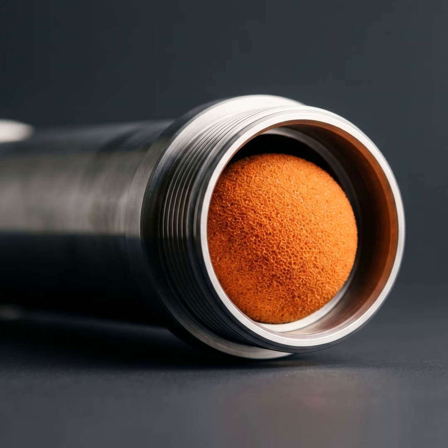It is the ultimate marriage of the digital and the physical realms. It really is. You have the software logic telling the system exactly when to release the balls, meticulously managing the 30-minute intervals, monitoring the flow rates. Right. And then you have the physical friction of the neoprene actually doing the dirty work that a human used to have to do with acid. And the net result is twofold. The chiller operates at peak thermodynamic efficiency permanently, saving vast sums of money. Right. And the human operator is restored to a position of safety and dignity, overseeing an intelligent system rather than risking their life to manually clean a decaying one.